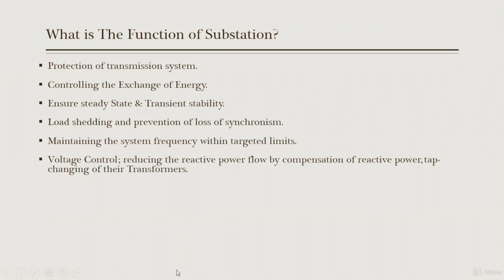Voltage control can be achieved by reducing reactive power flow through compensation of reactive power and tap changing of transformers. Our generators generate both active power P and reactive power Q. When the demand for reactive power increases, Q increases and our voltage starts to decrease.